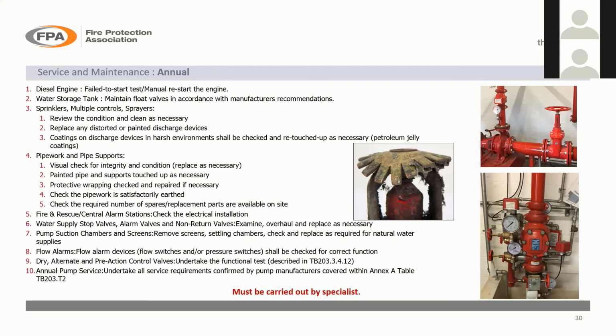Pipework supports often get overlooked, but it's important to look at your supports. I mean, if they're rusting away or they're damaged, if you get a sprinkler system operating, there's a good chance that when the fire pumps kick in, these operate with quite a jolt because they're operated on pressure. So the electric pumps and diesel pumps kick in very, very quickly. The pressure builds very, very quickly. So if your pipe supports are not up to speed and not capable of taking the shock loadings, then you could find your pipework on the floor and water going everywhere other than onto the fire.